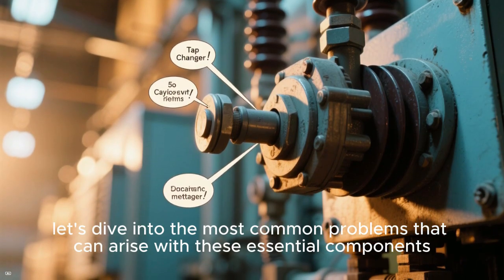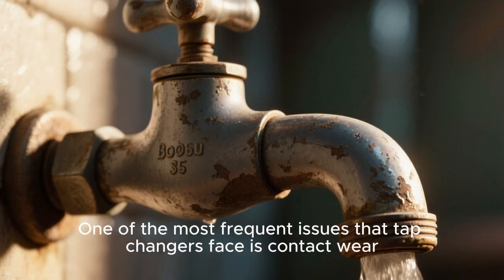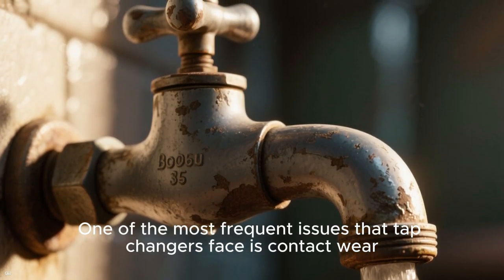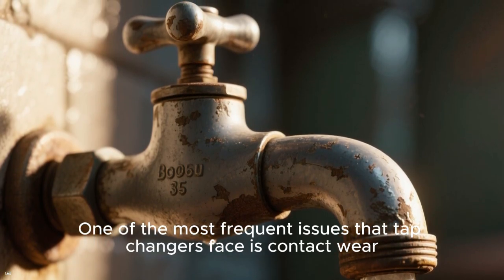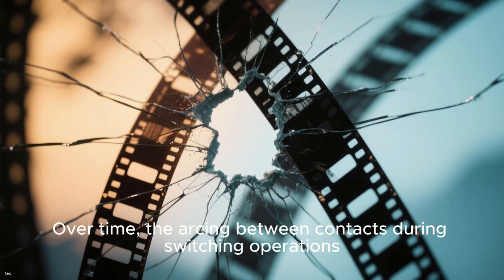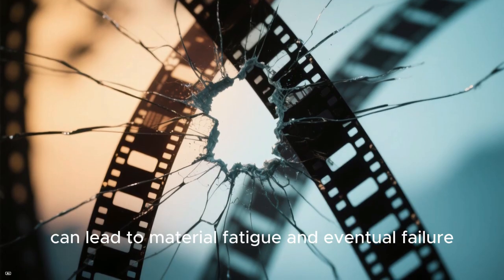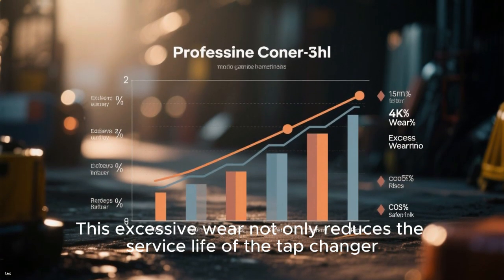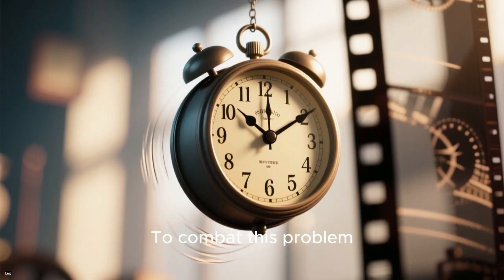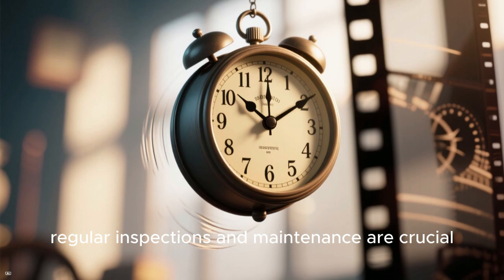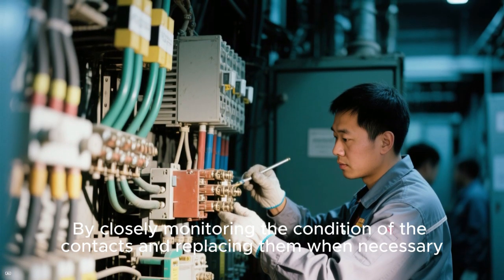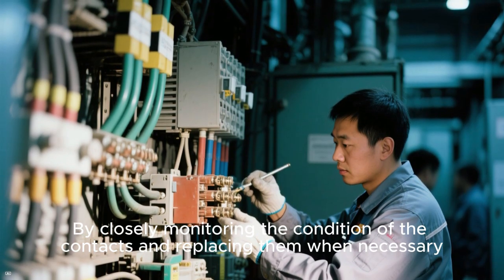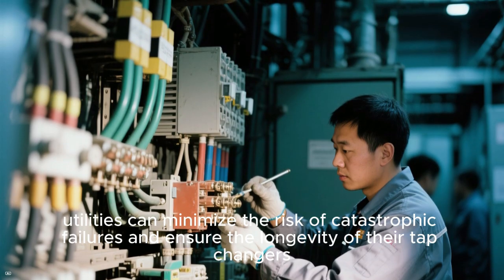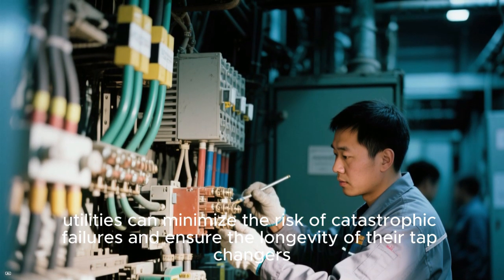Now that we've underscored the critical role of tap changers, let's dive into the most common problems that can arise with these essential components. One of the most frequent issues that tap changers face is contact wear. Over time, the arcing between contacts during switching operations can lead to material fatigue and eventual failure. This excessive wear not only reduces the service life of the tap changer, but can also result in increased maintenance costs and potential safety hazards. To combat this problem, regular inspections and maintenance are crucial. By closely monitoring the condition of the contacts and replacing them when necessary, utilities can minimize the risk of catastrophic failures and ensure the longevity of their tap changers.